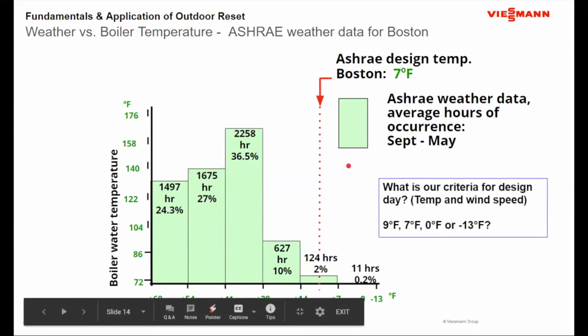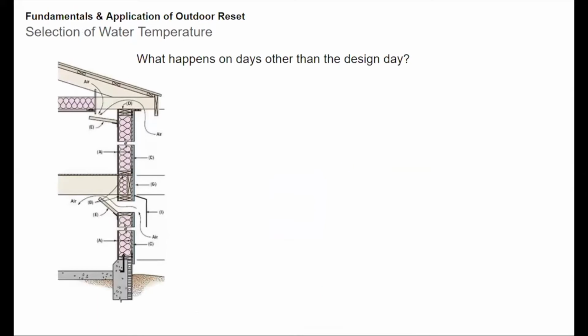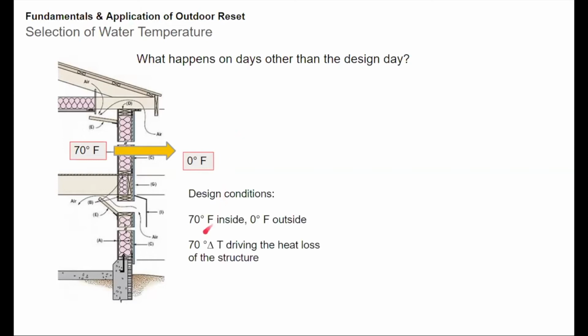Okay. So when we start to look at designing, and then carry on to actual operation, these are the conditions for my example that I'm designing for: 70 degrees on the inside, 0 degrees Fahrenheit on the outside. And that gives me a certain amount of heat transfer. But this building is sitting in Boston, Massachusetts, and not every day is 0. On that 0-degree day, I have a 70-degree delta T driving heat transfer through that wall, which ends up being a set amount of heat loss in BTUs per hour.